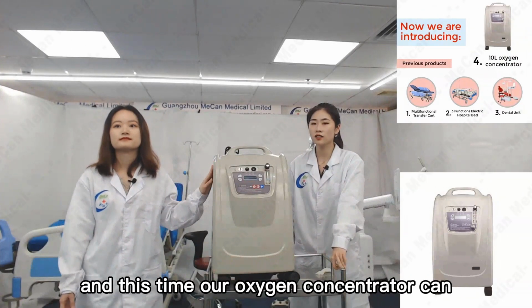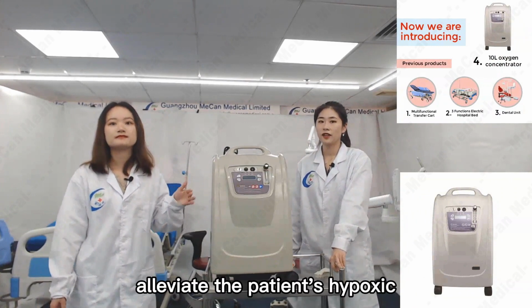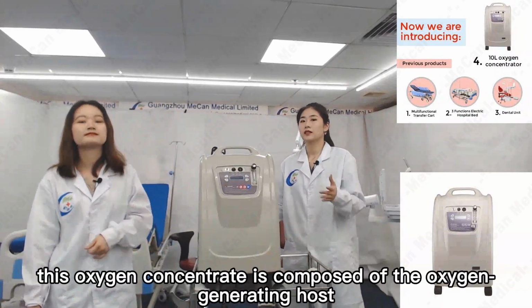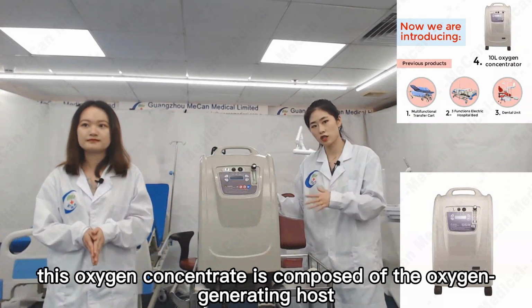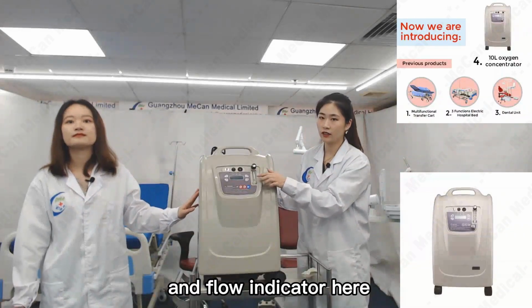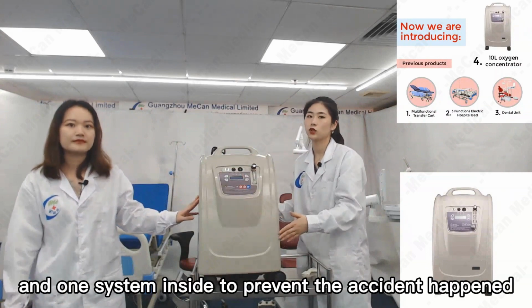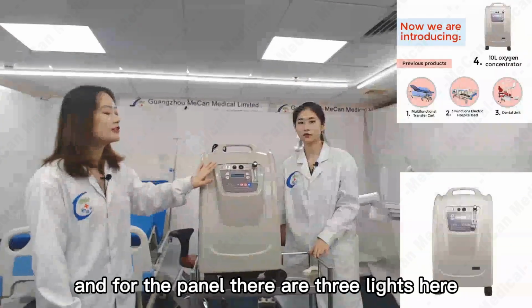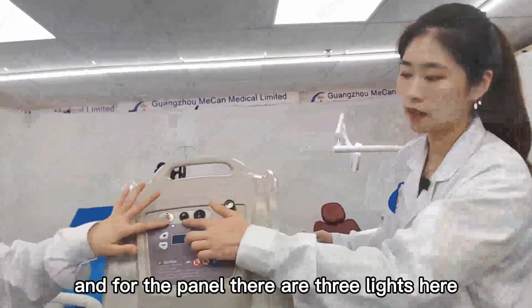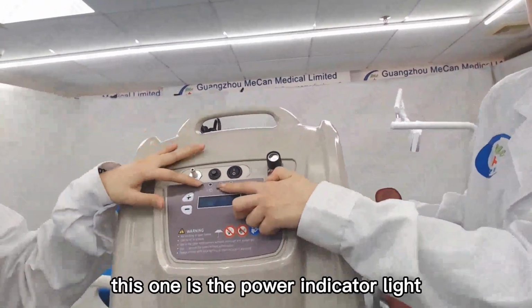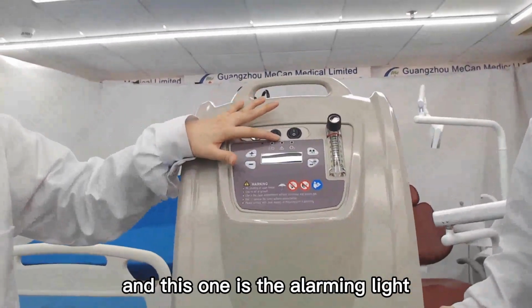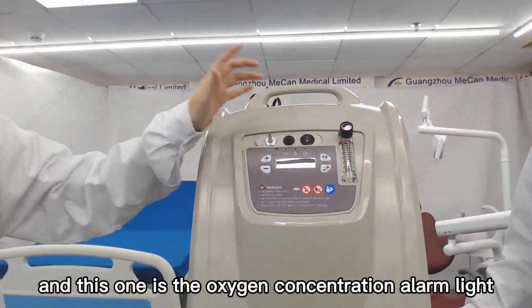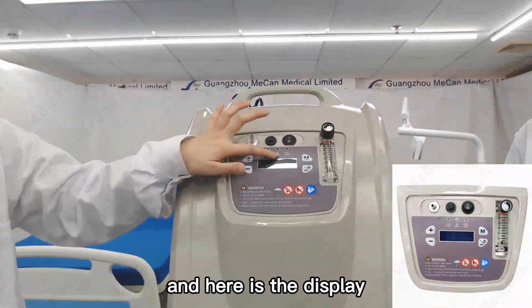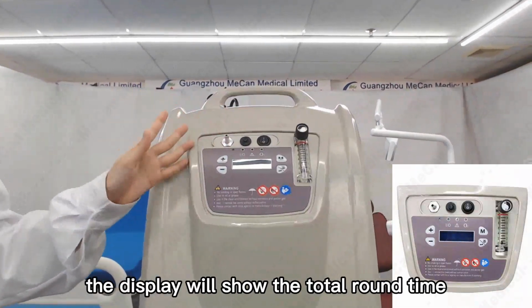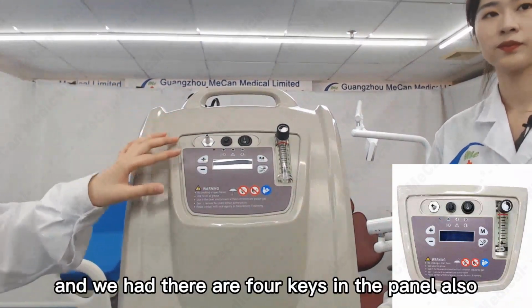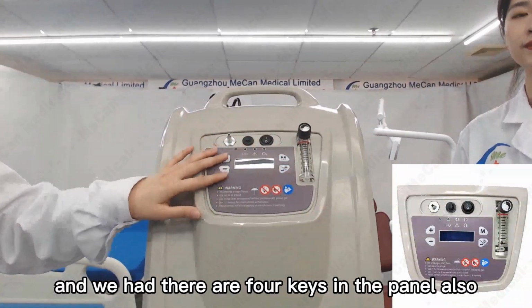And this time, our oxygen concentrator can alleviate the patient's hypoxia. This oxygen concentrator is composed of the oxygen generator host and the flow indicator here, with a warning system inside to prevent accidents. On the panel, there are 3 lights. This one is the power indicator light, this one is the alarming light, and this one is the oxygen concentration alarm light. And here is the display. The display will show the total runtime and the current runtime. There are also 4 keys on the panel.